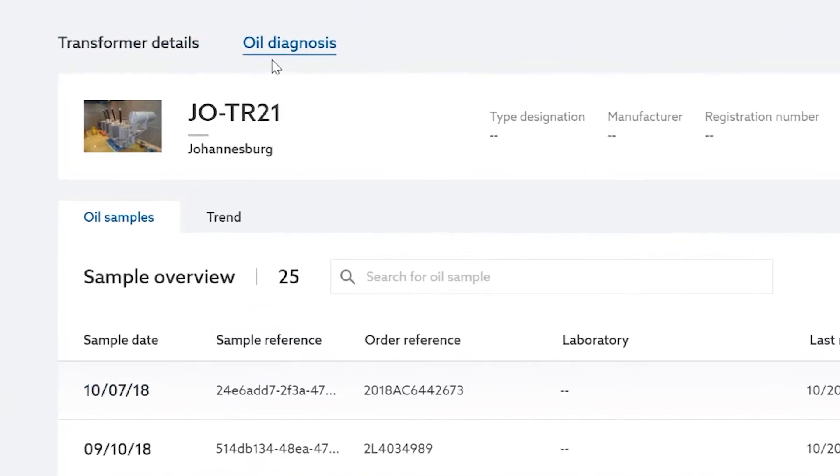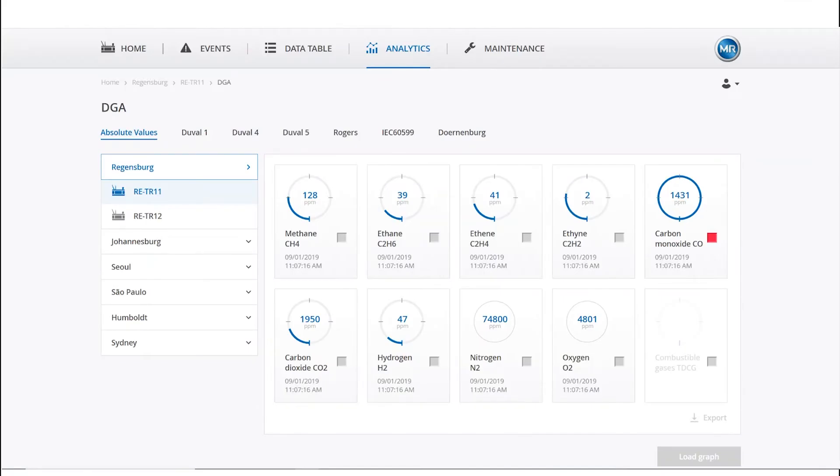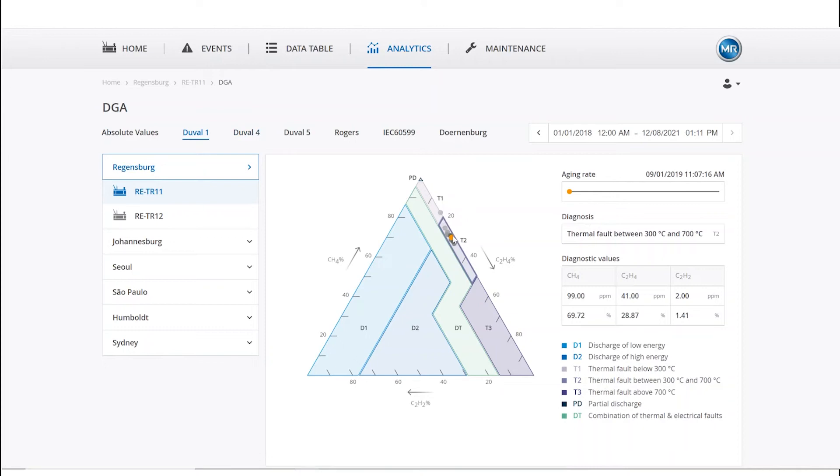One of the most common analyses for a transformer is the oil diagnosis. If your transformer is equipped with an online DGA sensor, all measurement data will be transferred to TESSA APM, where you can find them in a diagram and analyzed automatically with algorithms like Duval, Rogers, Doernenburg, IEC, and others.